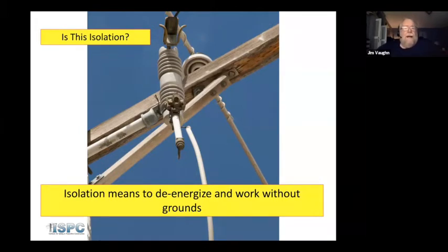But the actual distance, what we're going to be talking about, MAD, in a minute, and you know that on a distribution circuit, the MAD distance is about 2 feet 2 inches. Somewhere around there, or 3 feet, depending on what your utility standards are. And so we have people say, well, this isn't MAD because that distance isn't 3 feet. But that's not the same thing. In this case, this is a fixed device. If you take the barrel out, we have standards in the industry that set up the air gap necessary to be considered isolation across the switch. And in those standards, which we're not going to take the time to discuss, you'll find distances of isolation that are only 6, 7, 8 inches, and that is well within the gap that's on that switch.